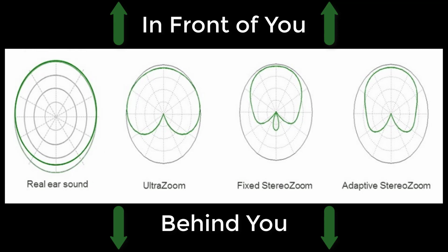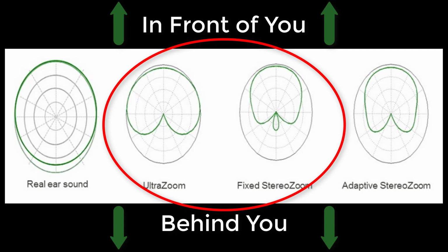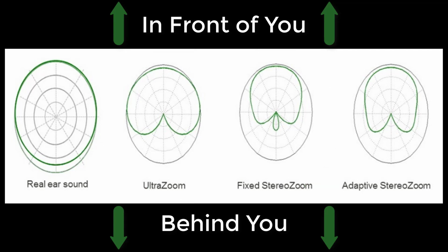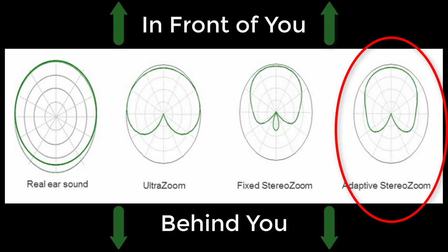As you enter more complex environments where there is background noise, you would ideally want the microphones to pick up sound primarily in front of you and maybe a little bit on the sides, as illustrated by the middle two images. Then, if you're in a noisy situation but the main talker is changing position, you may want an adaptive polar plot that changes based on the direction of the main sound source, as indicated by the image on the right.